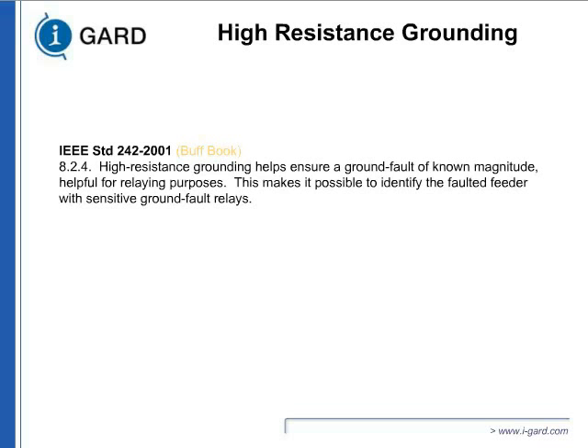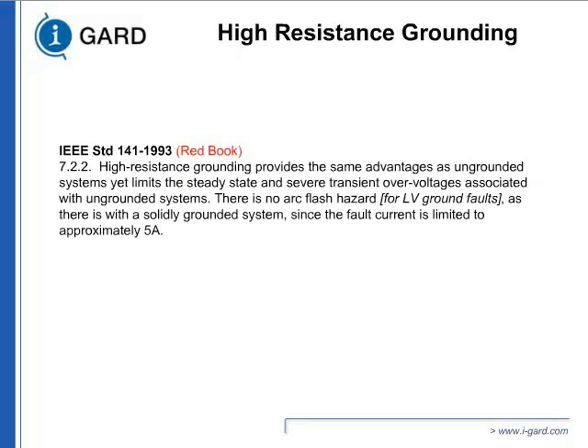The Red Book is still 1993 and is being revised right now, and you saw that quote before. High-resistance grounding provides the same advantages as an ungrounded system and more, yet limits the steady state. So it has the same benefits as ungrounded, but without the disadvantages of ungrounded. There is no arc flash hazard in the first ground fault because the first fault is very low magnitude and you can always detect it. So high-resistance grounding is the preferred method over an ungrounded system.